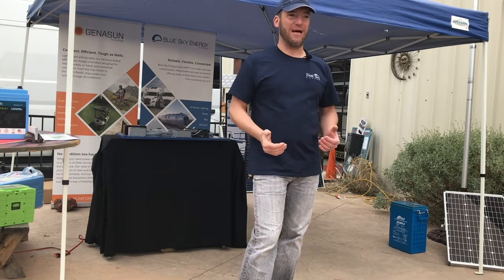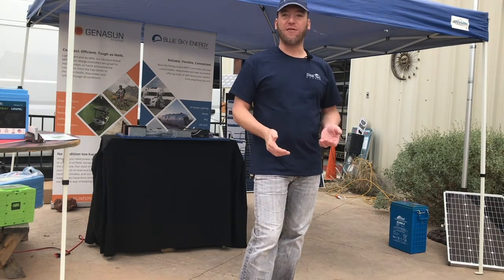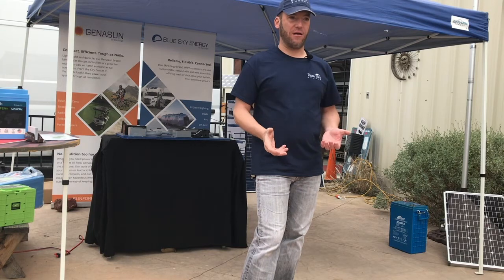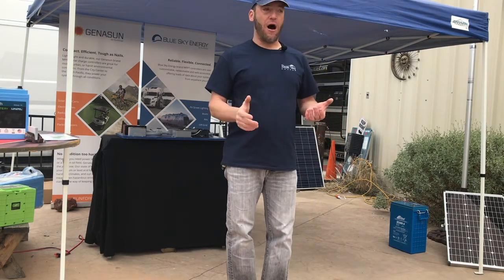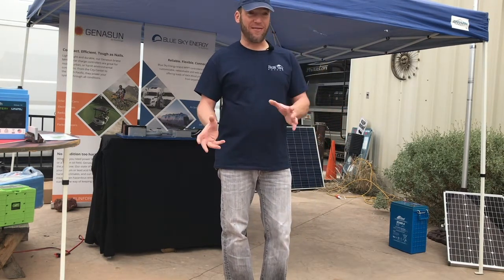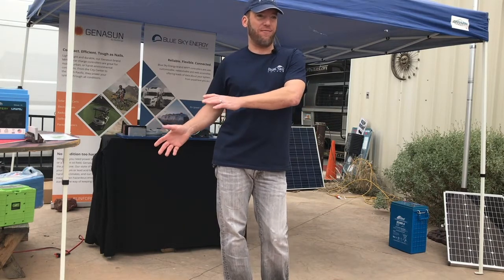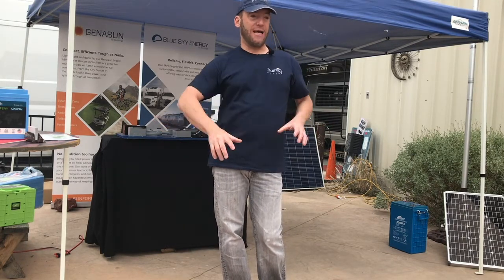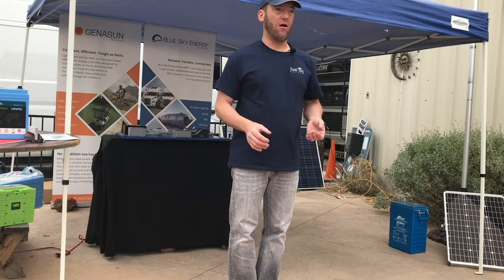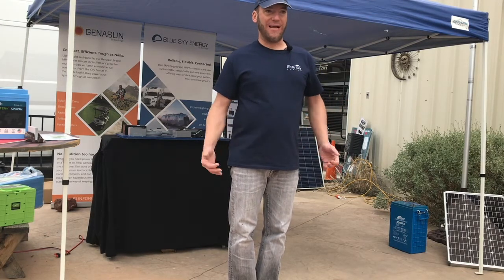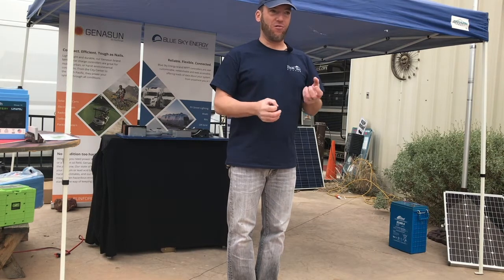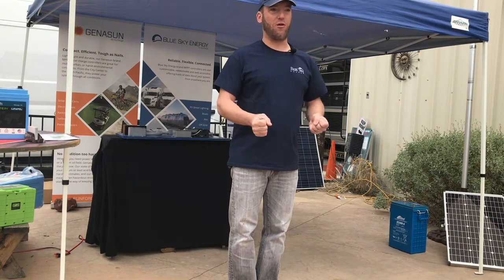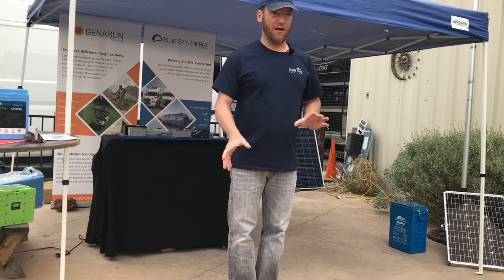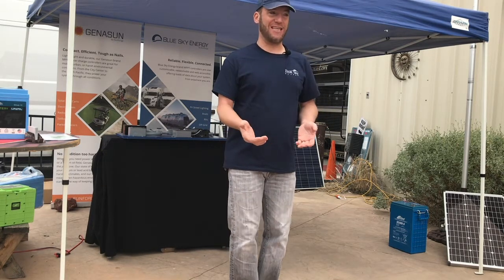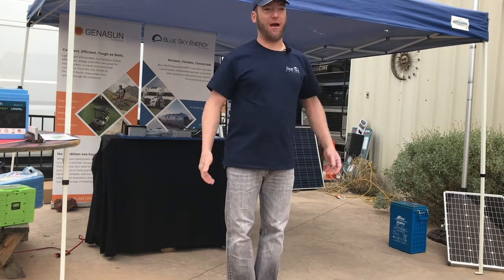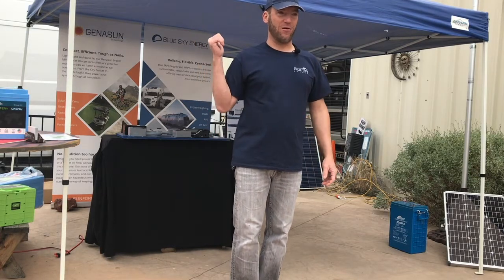So you want to oversize it by about 10 amps. Really, fuses are there for short circuit protection. You could put a 100 amp fuse on your controller—your battery's got hundreds and hundreds of amps available. If, God forbid, you had water damage on your controller or wires crossed, that short is going to go to the battery. So the exact fuse rating isn't super important. It's ideal not to overdo it, but if you have a 60 amp fuse that calls for 40, who cares—because I'm going to have 300 amps available if something goes wrong.